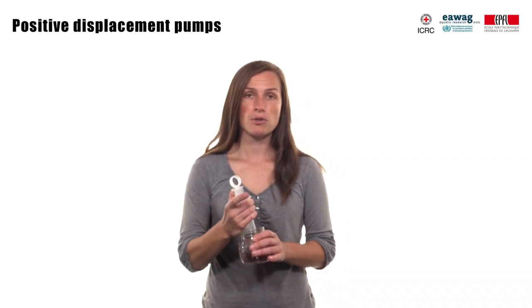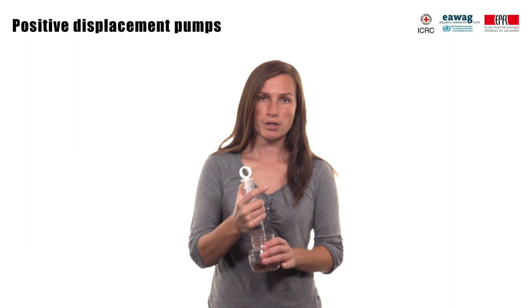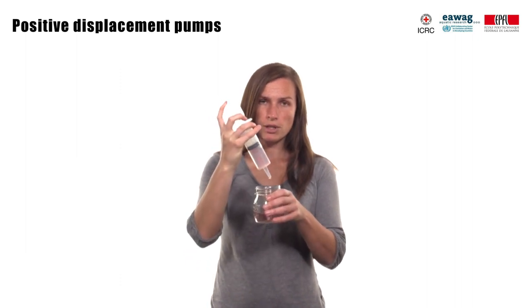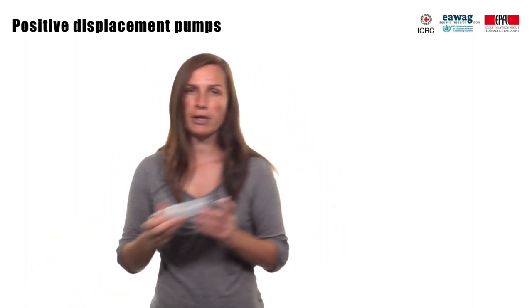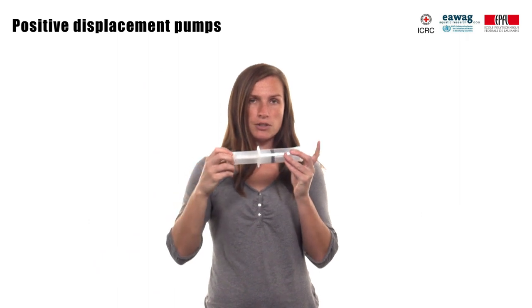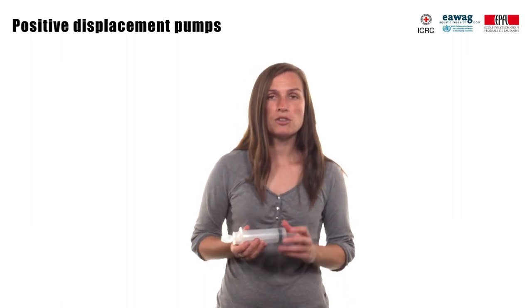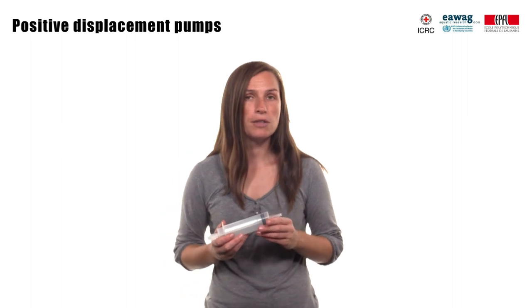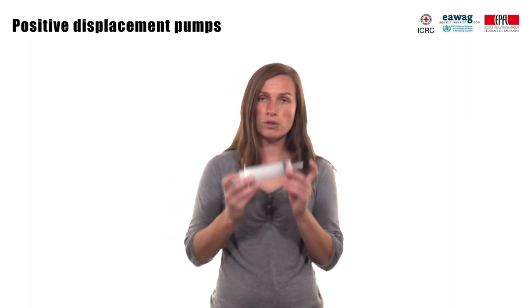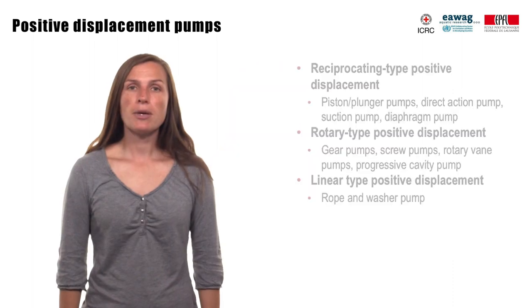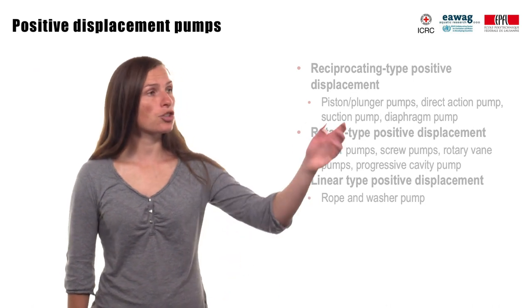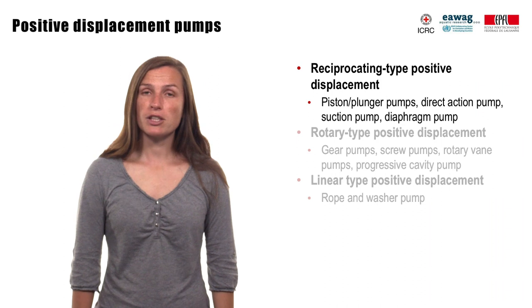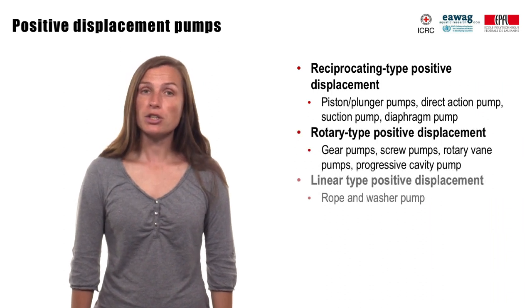A positive displacement pump makes a fluid move by trapping a fixed amount of water and forcing the trapped volume into the discharge pipe. Basically, the pump uses the principle of expanding cavity on the suction side and decreasing cavity on the discharge side. The volume remains constant during one cycle of operation, which means that theoretically positive displacement pumps should produce the same flow when the speed is constant, independently of the pressure on the discharge side. Depending on the type of mechanism used to move water, positive displacement pumps can be classified in three major groups: reciprocating type, rotary type, and linear type positive displacement.